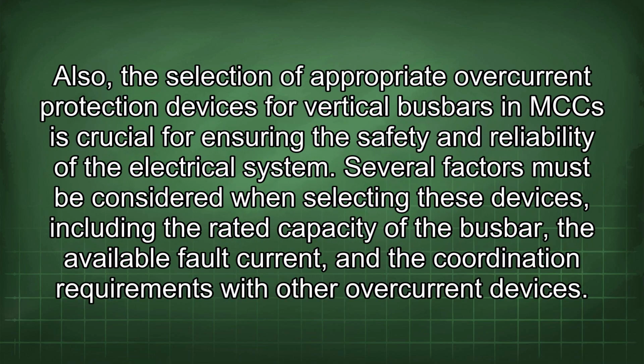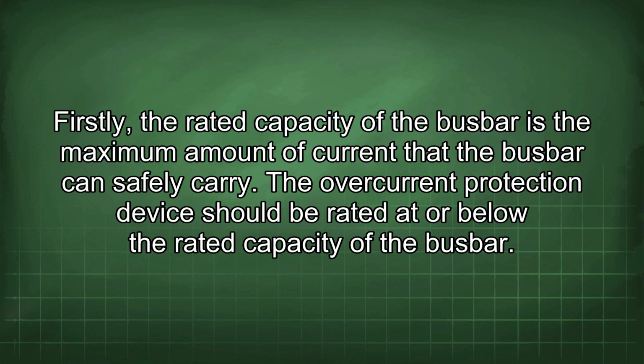Also, the selection of appropriate overcurrent protection devices for vertical busbars in MCC is crucial for ensuring the safety and reliability of the electrical system. Several factors must be considered when selecting these devices, including the rated capacity of the busbar, the available fault current, and the coordination requirements with other overcurrent devices. Firstly, the rated capacity of the busbar is the maximum amount of current that the busbar can safely carry. The overcurrent protection device should be rated at or below the rated capacity of the busbar.